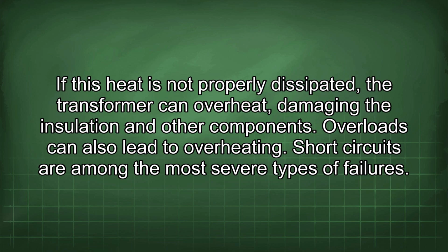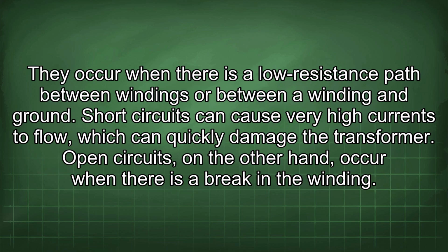Short circuits are among the most severe types of failures. They occur when there is a low resistance path between windings or between a winding and ground. Short circuits can cause very high currents to flow, which can quickly damage the transformer.